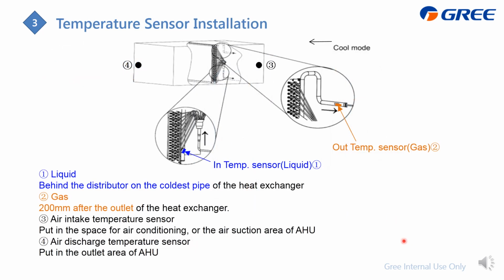Next is for the temperature sensor installation. First is for the liquid, which is the pipe in, and the location should be at the coldest pipe, which is around here, and the pipe out, which is for the gas, and it should be 200 millimeter just after the outlet of the heat exchanger, around here.